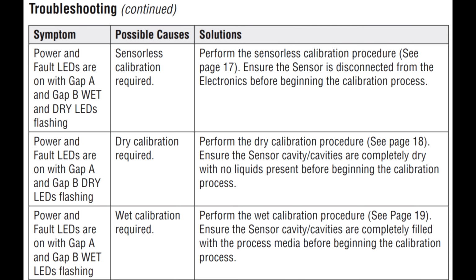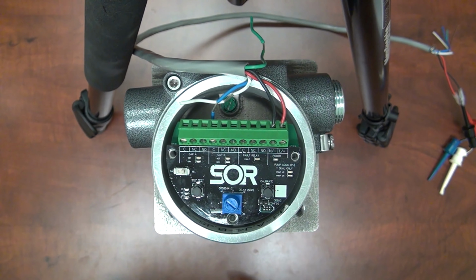Now, let's look at the fault states that could occur. You will know a fault state has occurred when, upon powering up the device, the red fault LED is lit. Each fault state requires a different type of calibration to correct. Next, let's perform the 3 different calibrations that may be required for the device.